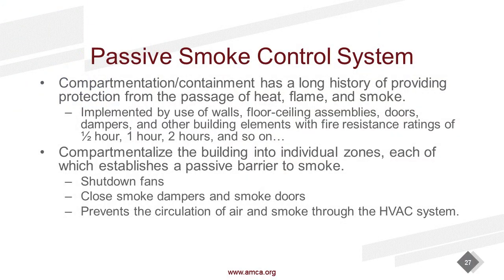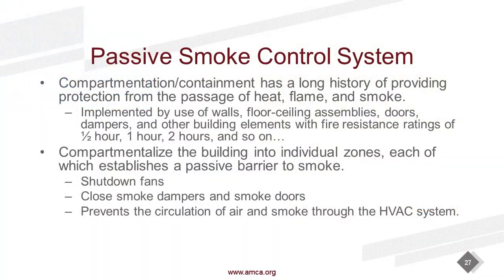So again, passive smoke control is the way we use smoke dampers, just to close, prevent the spread of smoke. Pretty simple. We call that Chapter 7 of the International Building Code. So if we're looking at the IBC, we see Chapter 7, fire and smoke protection features, and Chapter 9 as well. Engineered smoke control systems will fall in Chapter 9, but Chapter 7 is going to be your passive dampers, and again, that's that compartmentalization, the containment part of the dampers.